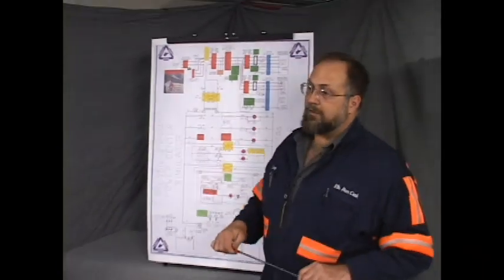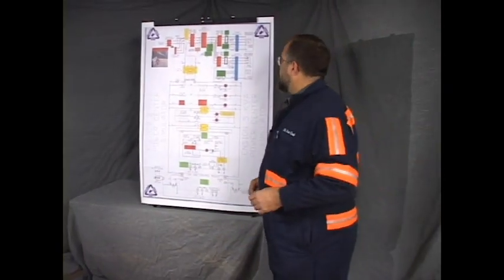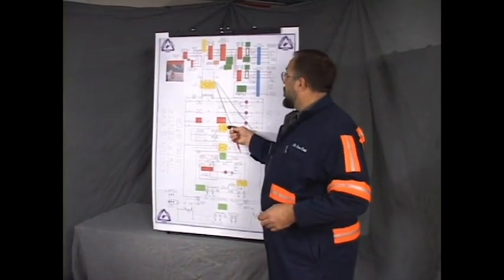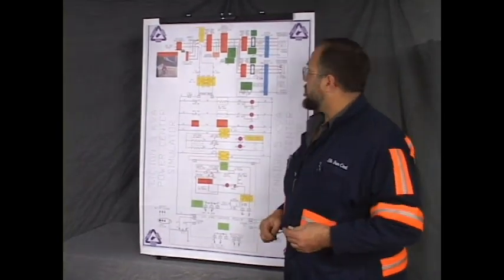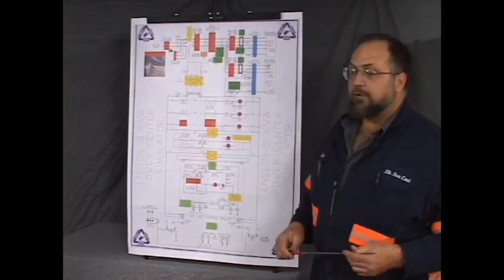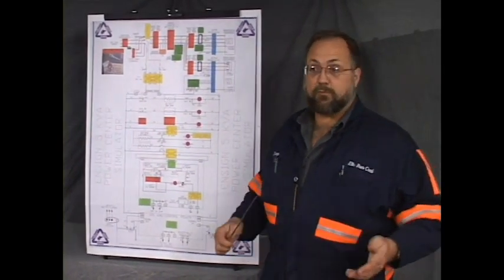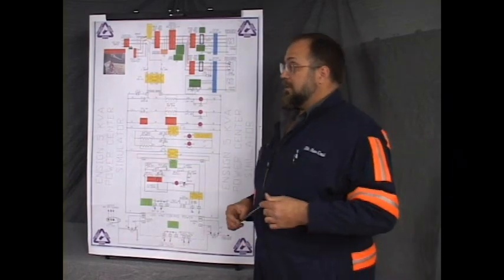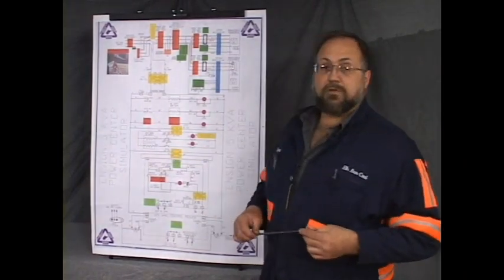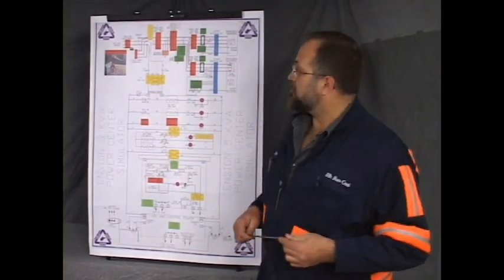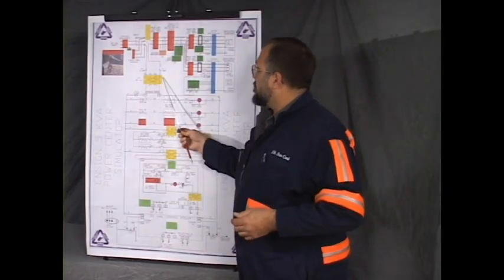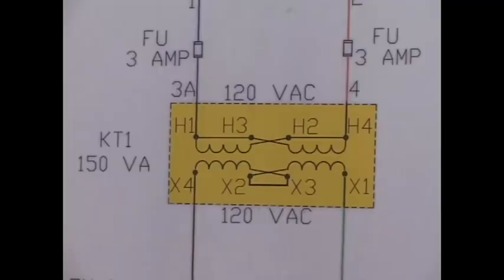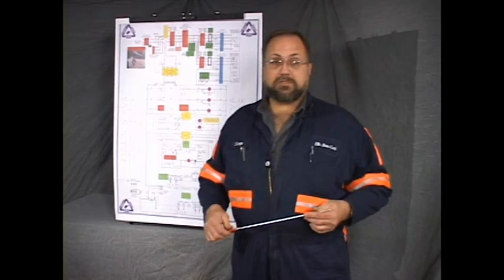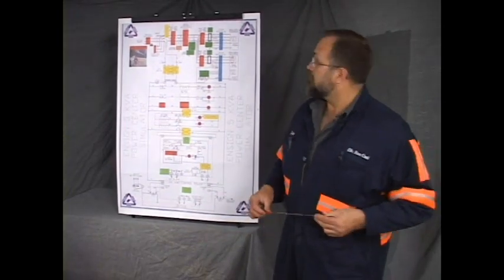Now, normally on a power center skid that you'd be working on underground, the primary would be the 480 volts, the same as the rest of the skid. The primary supply for the control would be 480. But the simulator runs on 120 volts for the classroom here. So it has a 120 volt primary source. It's a one-to-one transformer. There's no step down or step up.